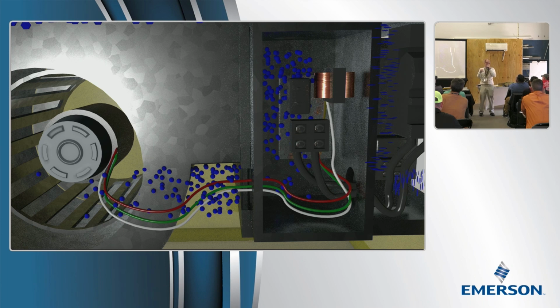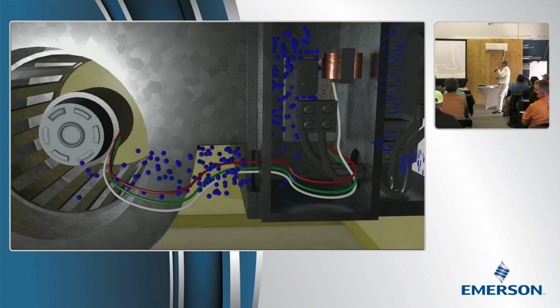You have to add a little something to the Romex connector or it's going to leak. Sometimes it's just a knockout and they don't even use a Romex connector. It's just wide open. But this is the infiltration that causes things to rust. So anytime you're in one of these cold cabinets and you see a lot of rust, look for that path to outside that those molecules are taking. This one also has the built-in circuit breaker. It always leaks around those.